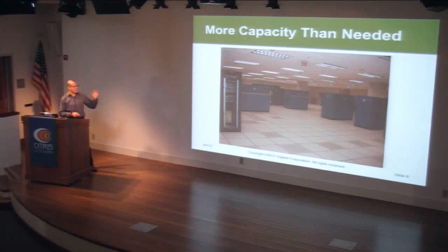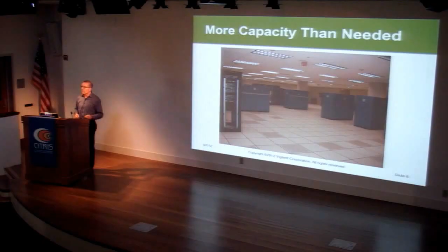So, more capacity than needed. Here's a visual example of that. This is a state of California data center, and this is actually just 180 degrees from the photo I showed you before. They haven't filled this in yet, and yet they have all these air conditioners. Before we got in there, all of them were running all the time, because in fact they had tried to manually shut some of these off since they knew they didn't need it. These guys aren't idiots, they know it doesn't all need to be on all the time. But when they shut them off manually, they'd get a shift in load, something would change, and they'd get an incident at 3 o'clock in the morning. So it's just like, forget it, it's all on all the time. It's got to be that way.